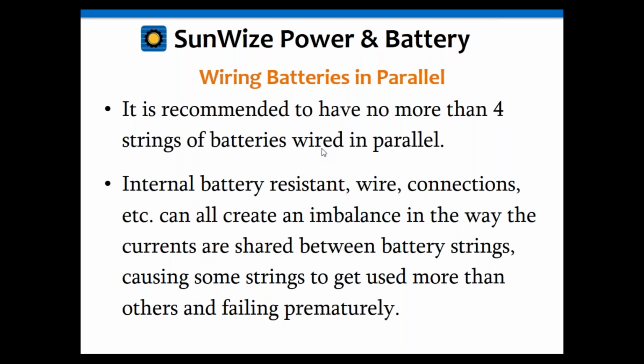The reason for this is internal battery resistance. Even batteries coming off the same line at the same time, all manufactured together, will still have some minor variance—there's always some tolerance to this stuff, nothing's perfect. Because of that, the internal resistance of these batteries will be just slightly off, not a lot, but a little. You'll find the same thing with the wire and connections—they won't be exact, there's always a slight difference. The more you have in parallel, the greater this imbalance could possibly be. So by minimizing the strings, you minimize the risk of imbalance between the batteries, the connections, and things like that.